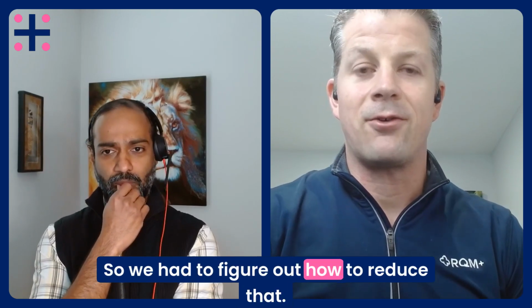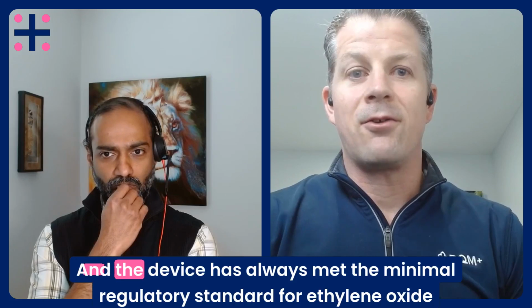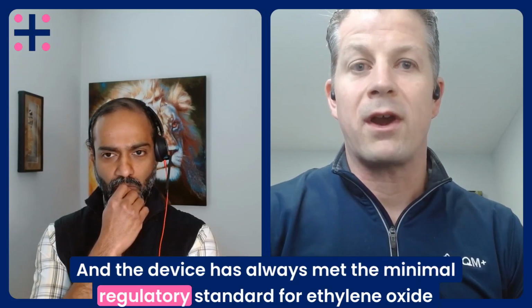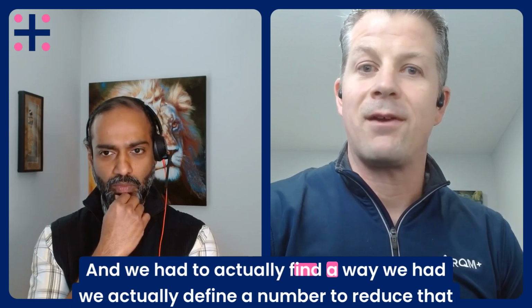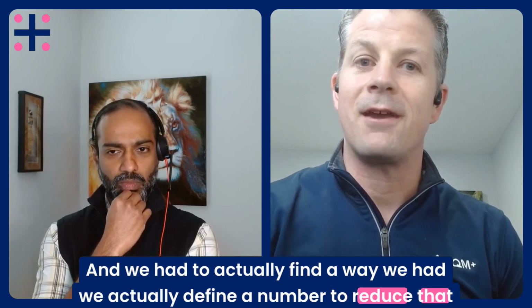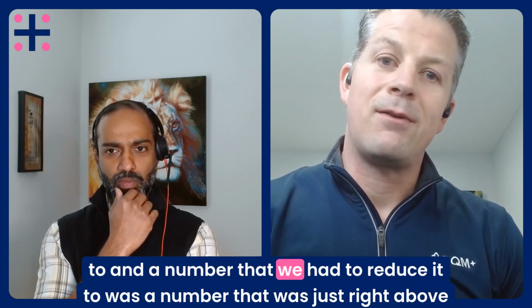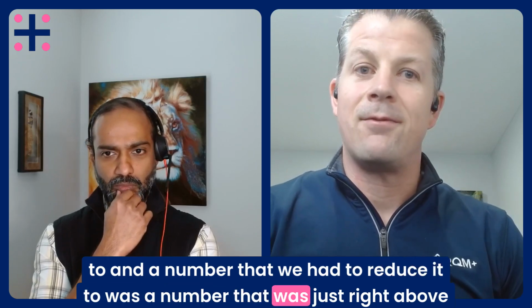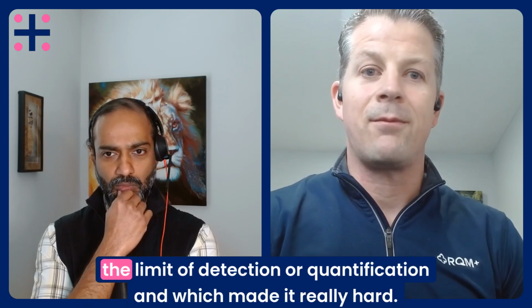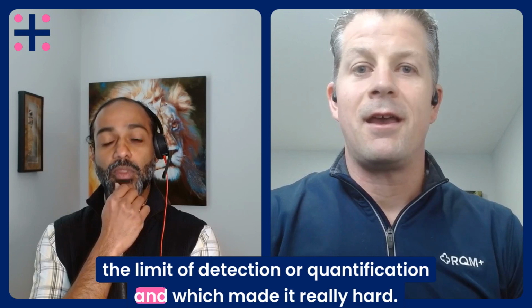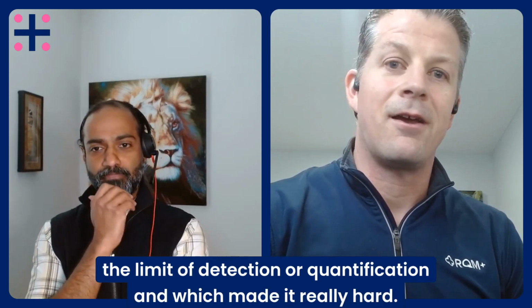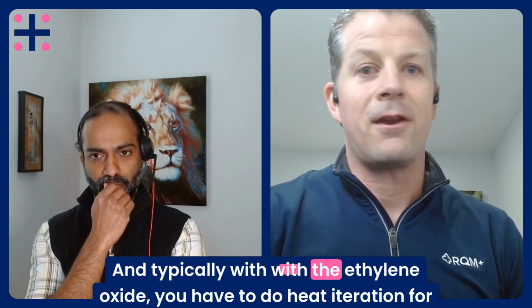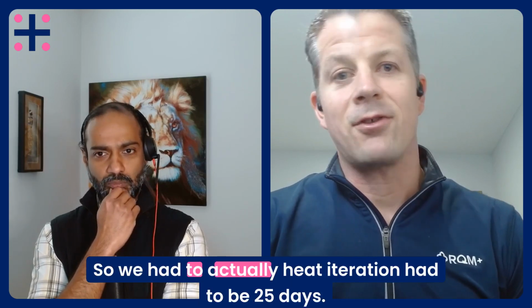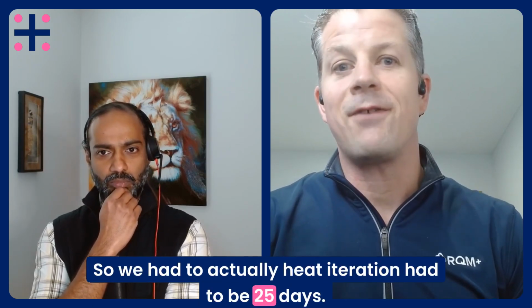So we had to figure out how to reduce that. And the device has always met the minimal regulatory standard for ethylene oxide residuals. And we had to actually find a number to reduce that to. And a number that we had to reduce it to was a number that was just right above the limit of detection or quantification, which made it really hard. And typically with the ethylene oxide, you have to do heat aeration for 2 days. So we had to actually, heat aeration had to be 25 days.